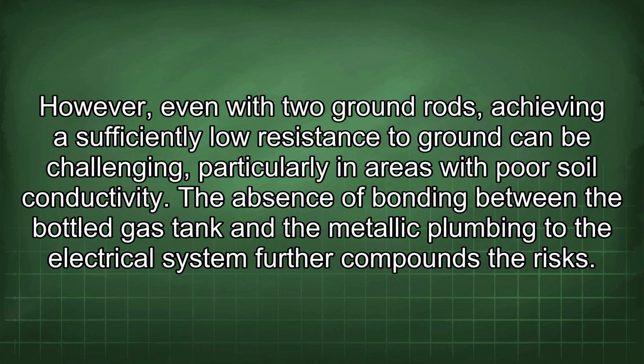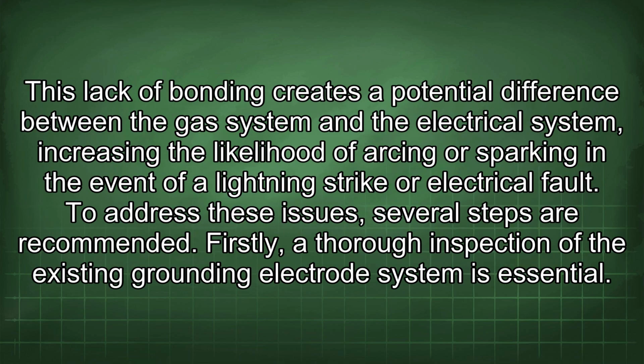However, even with 2 ground rods, achieving a sufficiently low resistance to ground can be challenging, particularly in areas with poor soil conductivity. The absence of bonding between the bottled gas tank and the metallic plumbing and the electrical system further compounds the risks. This lack of bonding creates a potential difference between the gas system and the electrical system, increasing the likelihood of arcing or sparking in the event of a lightning strike or electrical fault. To address these issues, several steps are recommended.